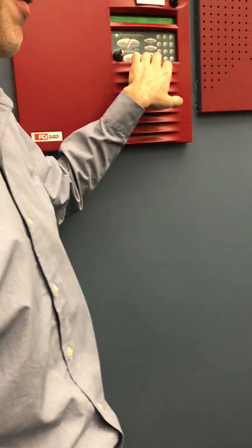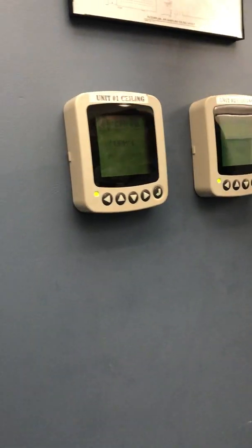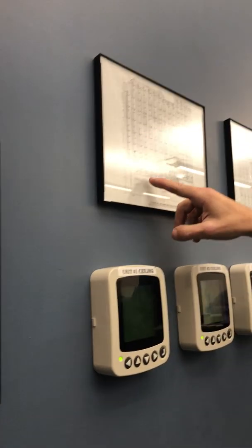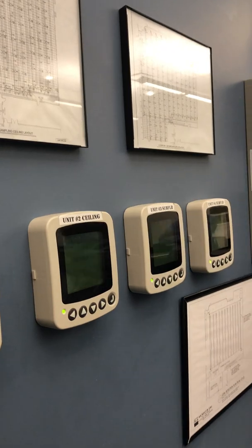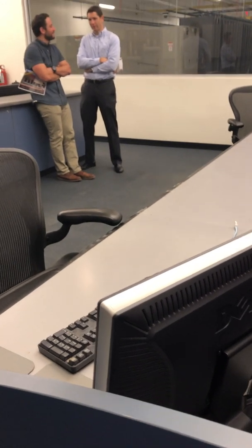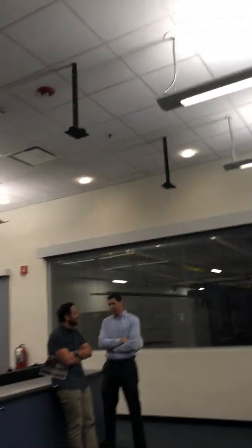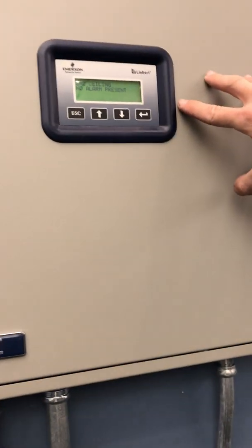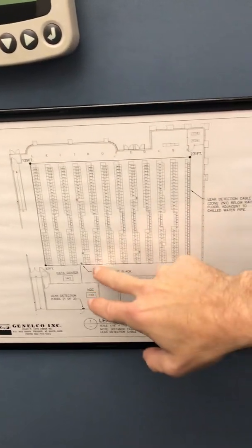This handles the conventional office spaces. This is just batteries. Not wanting to rely solely on the ceiling mounted smoke detectors, we have air sampling, which draws above the ceiling and then below the floor. And we also tie into the conventional smoke detectors, which are in the Liebert CRAC units. And those come from the factory, so we just made use of them as that. We also have leak detection, which follows the pipe path around the perimeter of the room, and then the stub overhead, which is reflected in ceiling and subfloor.